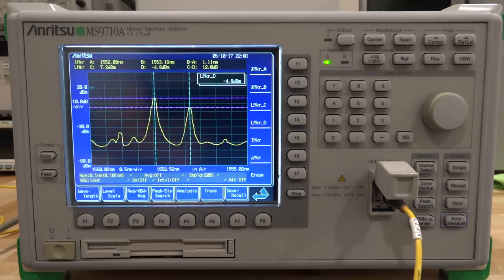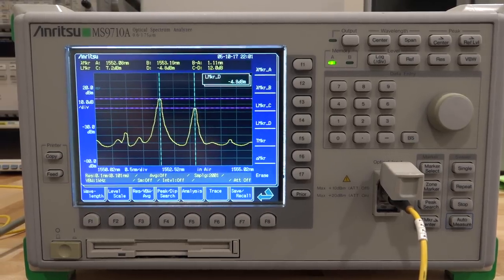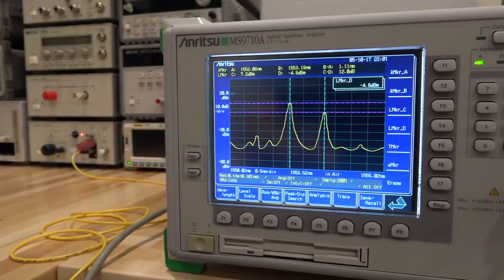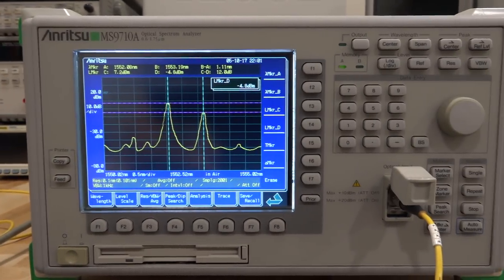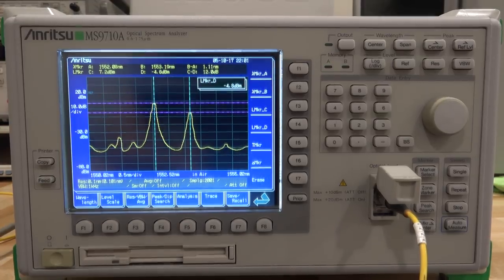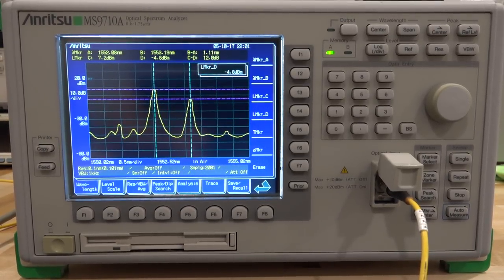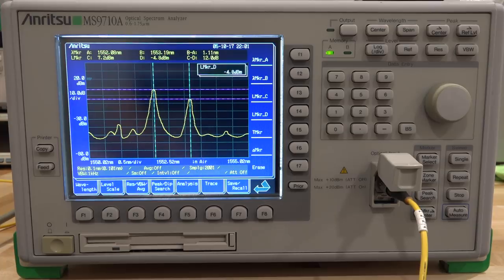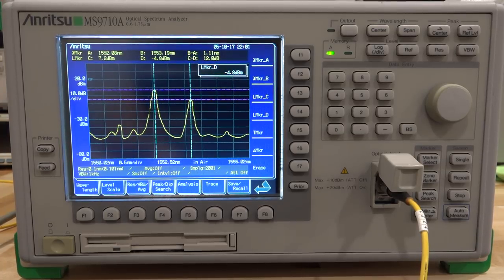So yeah, I really can't call this a repair. It's more of just a fun little thing to try and disassemble this and reassemble it and take a look. I know you probably wanted to see all the optical bit, but I wanted to try it out, at least to see if we can get it to work before we take it apart, because usually those things, as you know, sometimes you can't even open them because they are purged with a non-reactive gas, like a noble gas, or maybe purged with nitrogen so that oxidization and deterioration of mirrors and things like that wouldn't happen. So opening it sometimes is detrimental or completely ruins the instrument. So that's why I didn't want to do it in this video.